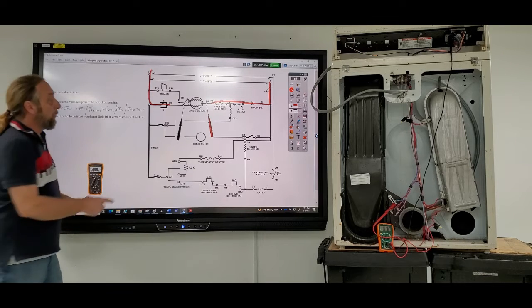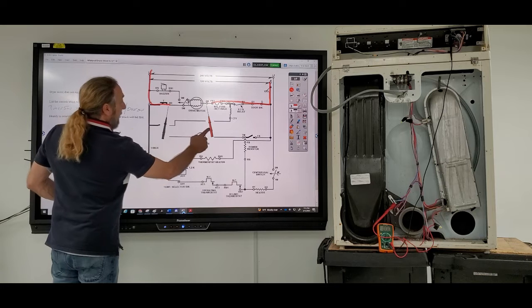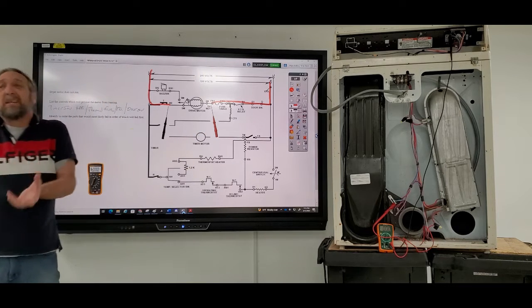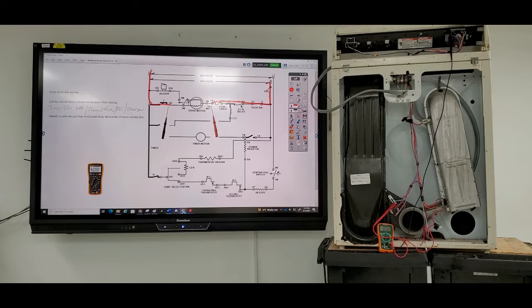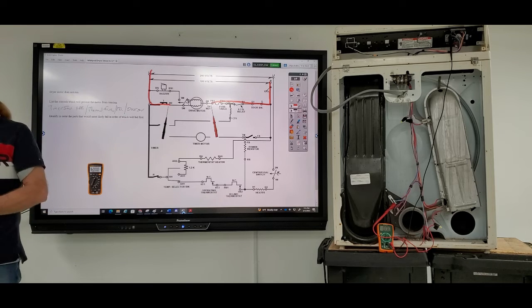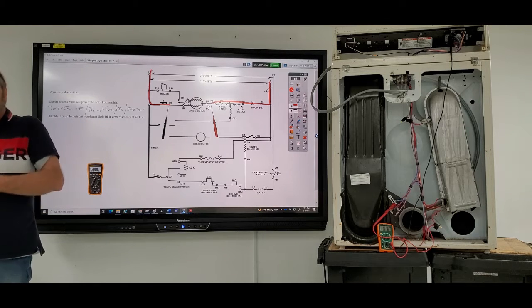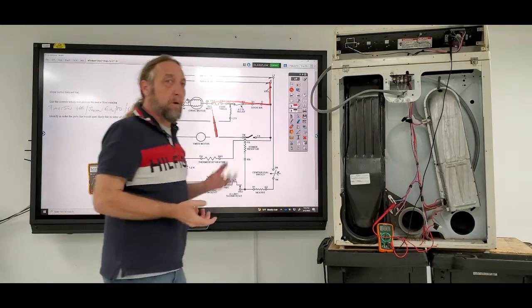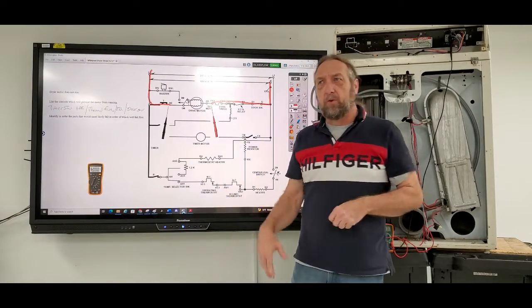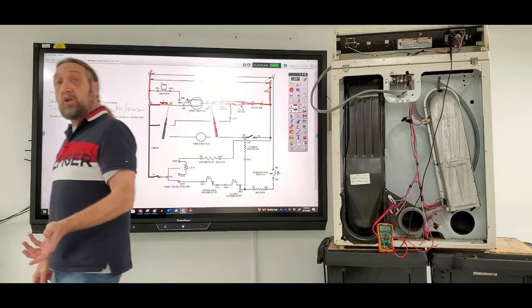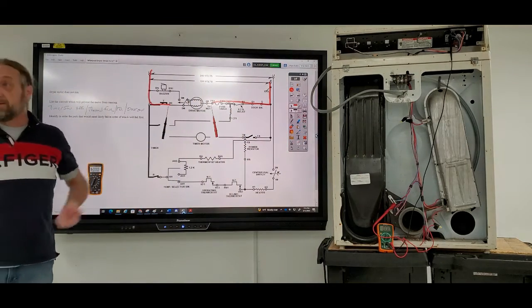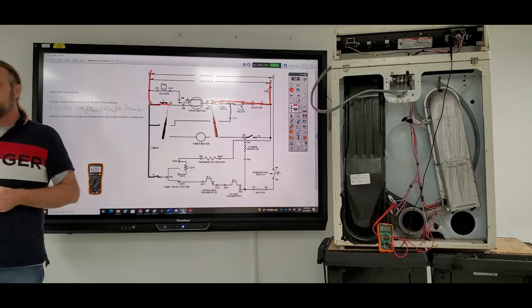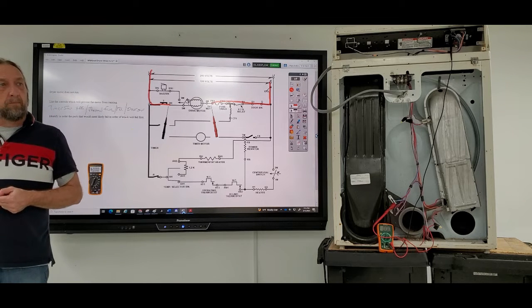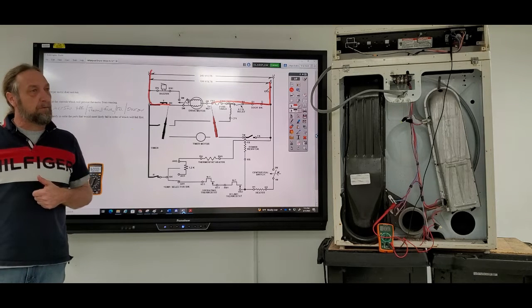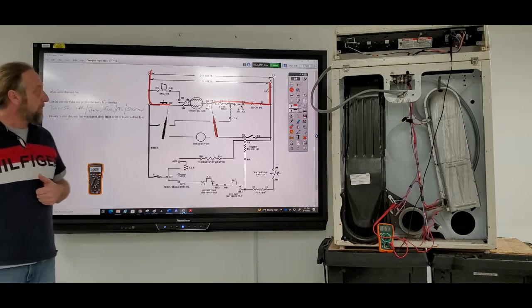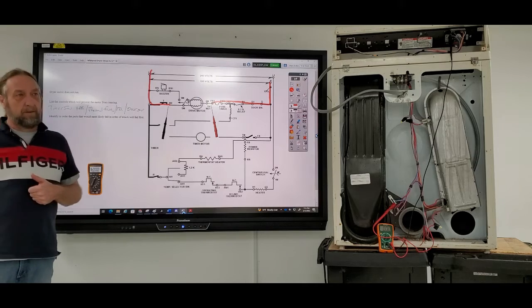Let's look at it the other way though. Let's just say we were at this point here and here, and I didn't have voltage coming to that point, right? What's my next test? Do I check the door switch? Do I check the thermal fuse? Do I check the timer switch? Do I check the timer motor or timer contact? You move your meter leads. And where do I move my meter leads? You expand your search. So instead, just to be safe, you go to yellow, and then from RE you go to FS2.